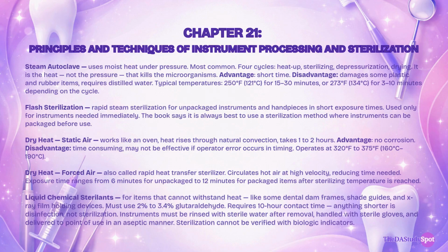And the last sterilization method, liquid chemical sterilants. These are for the instruments that cannot withstand heat. For example, dental dam frames, shade guides, and X-ray film holding devices. And 2% to 3.4% of glutaraldehyde must be used. It does require a 10-hour contact time, so don't think you can just flash sterilize these, because anything shorter is disinfection, not sterilization, and we know those two are not the same.